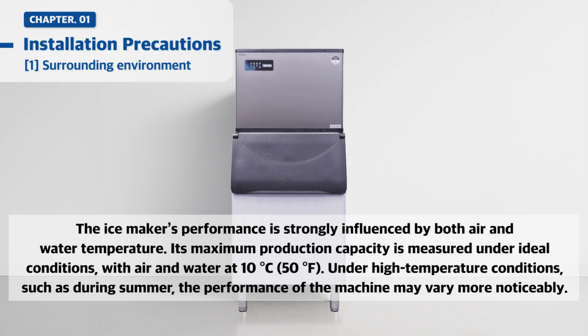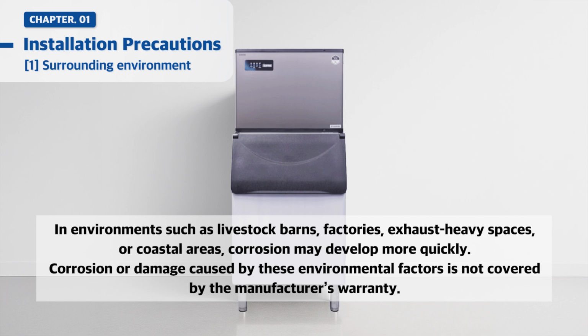The ice maker's performance is strongly influenced by both air and water temperature. Its maximum production capacity is measured under ideal conditions, with air and water at 10 degrees Celsius. Under high temperature conditions, such as during summer, the performance of the machine may vary more noticeably. In environments such as livestock barns, factories, exhaust-heavy spaces, or coastal areas, corrosion may develop more quickly. Corrosion or damage caused by these environmental factors is not covered by the manufacturer's warranty.